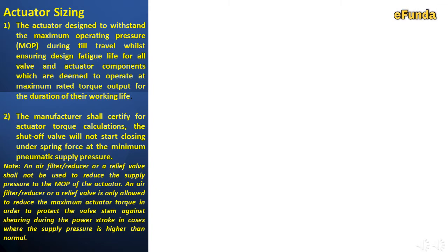Actuator sizing. The actuator is designed to withstand the maximum operating pressure, that is MOP, during full travel whilst ensuring design fatigue life for all valve and actuator components which are deemed to operate at the maximum rated torque output for the duration of their working life. The manufacturer shall certify the actuator torque calculation. The shutoff valve will not start closing under spring force at the minimum pneumatic supply pressure.